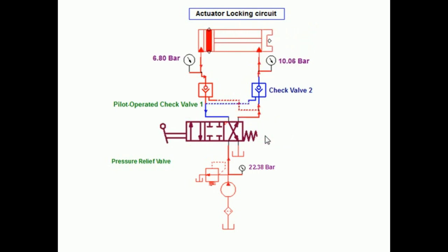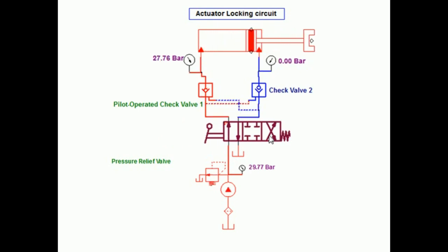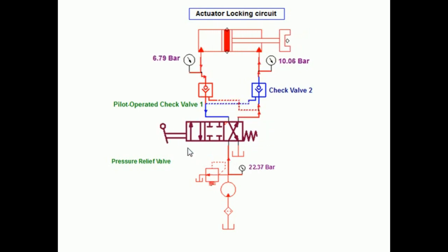An external force acting on the piston rod will not move the piston in either direction because reverse flow through either pilot check valve is not permitted under this condition.